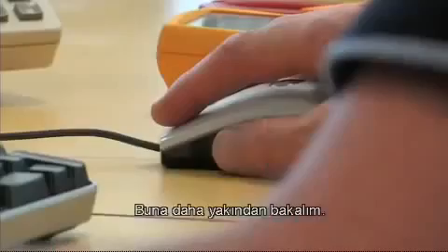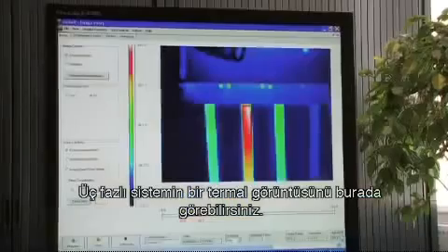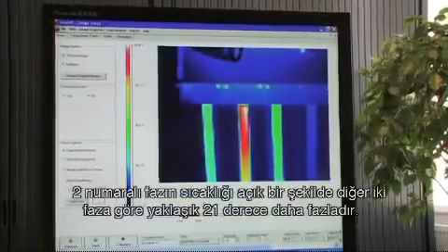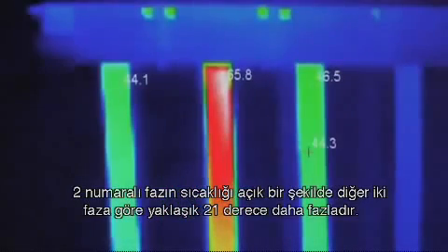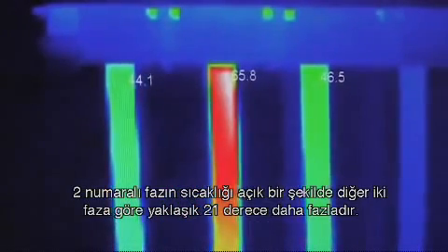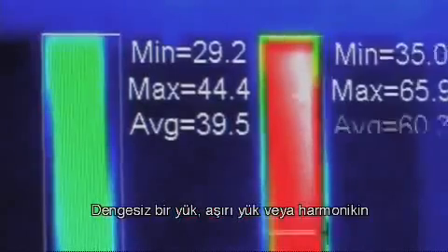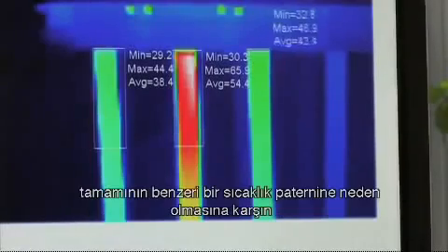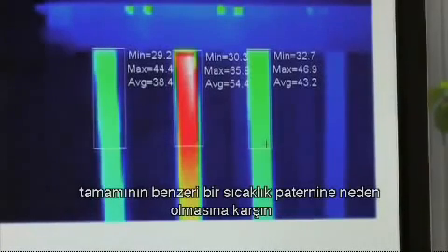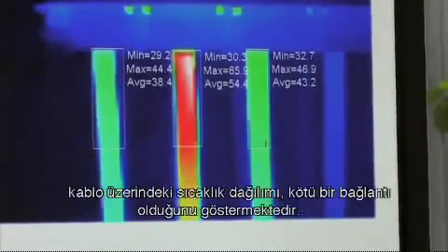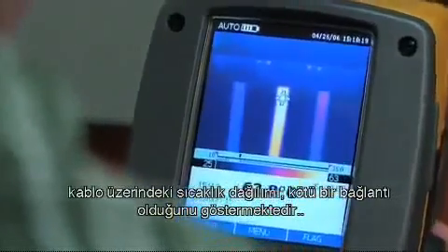Let's have a closer look. Here you can see a thermal image of a three-phase system. The temperature of phase 2 clearly shows about a 21 degrees higher temperature than the other phases. This is a clear indication that something is wrong. The temperature distribution over the cable suggests a bad connection, although an unbalanced load, overload, and harmonics can all result in a similar temperature pattern.